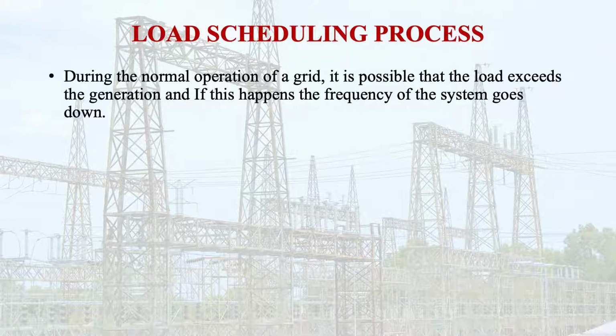Now let us come to load shedding. What is this load shedding? You have heard this word, load shedding. So what does it mean? During the normal operation of the grid, it is possible that load exceeds the generation. What will happen if the load exceeds the generation? Your generation is less and your demand is high. If this happens, the frequency of the system goes down, because frequency indicates the balance between the generation and the load. So the frequency of the system goes down.